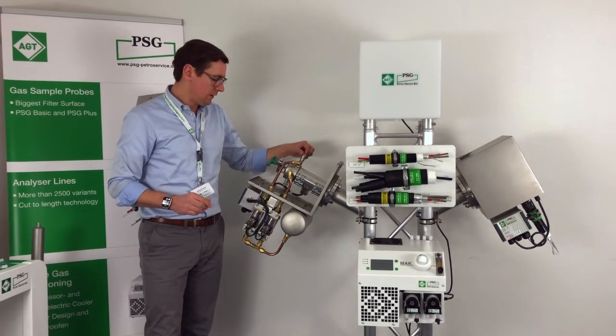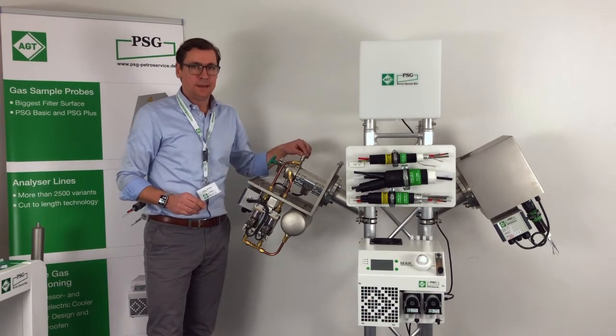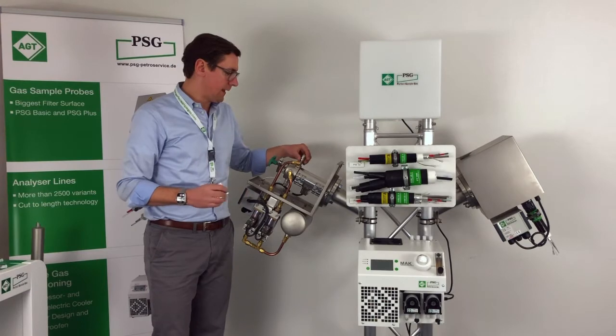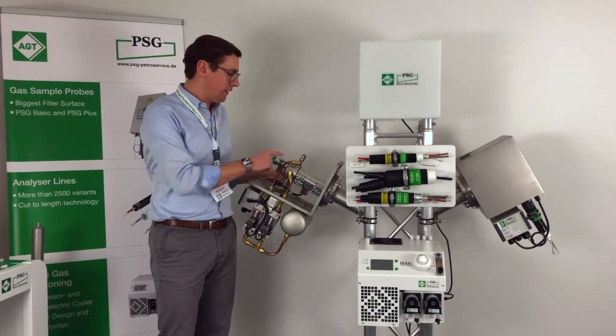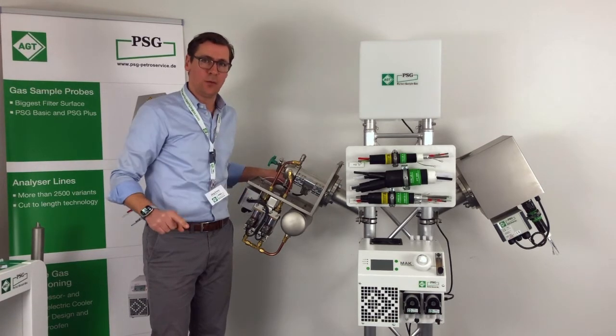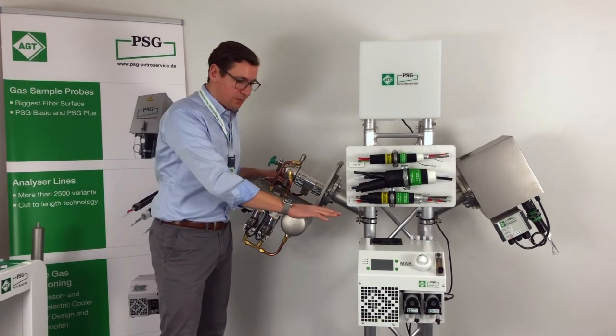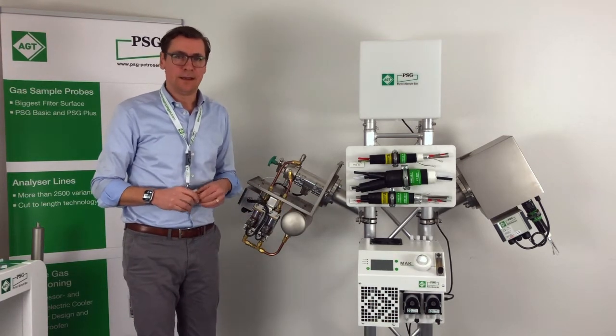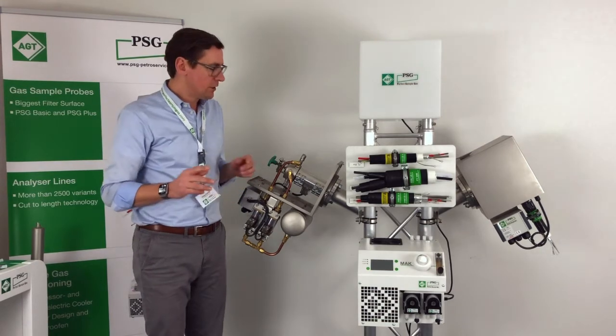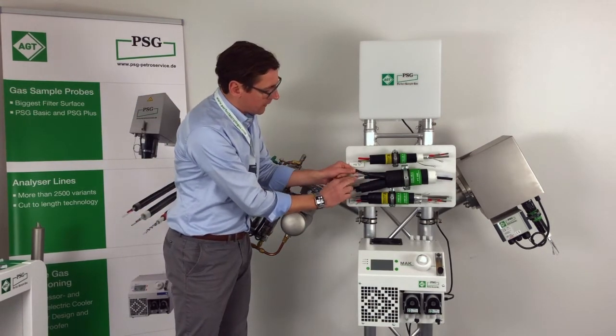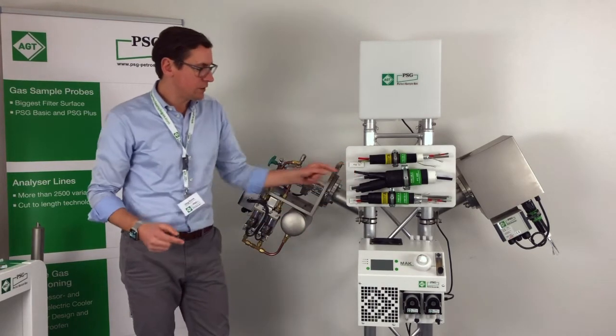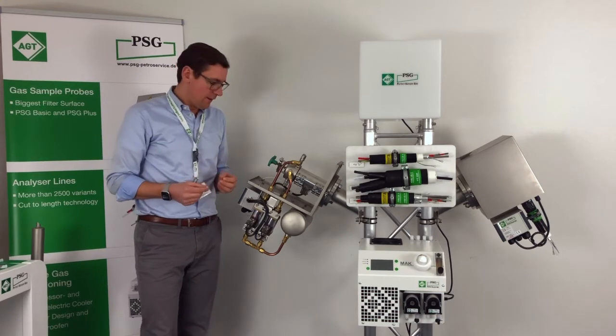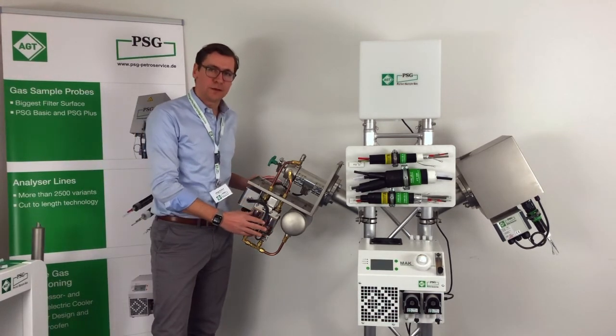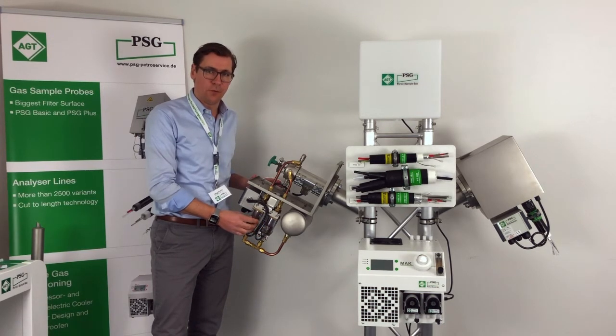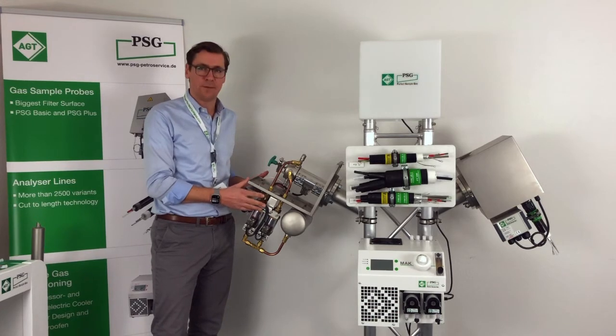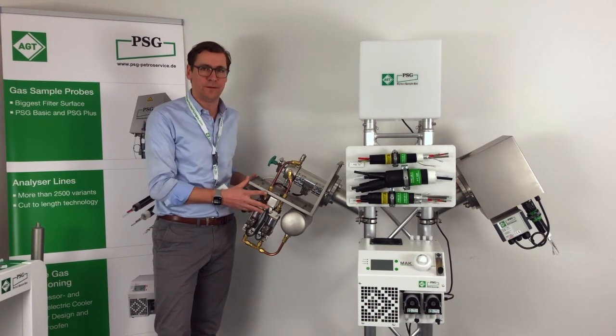Then you see here is the calibration port. Many legal requirements say that the testing gas has to run from the probe the entire way via the heated sample line through the cooler to the analyzer in order to be compliant with the legal requirements. So we also include another line here which is used for the calibration gas. Finally, you can also see the need for the back purging of the probe. If you are interested in the back purging concept of our PSG Plus probe, please refer to the video of the PSG Plus.